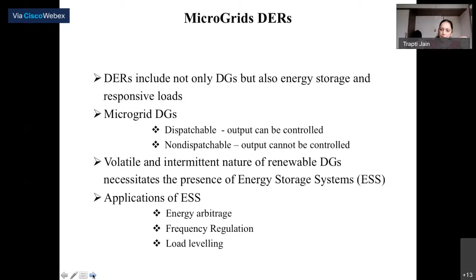We need to maintain the frequency. As shown in the first figure, 60 hertz is the frequency we want to maintain, and the allowable band is 59.95 to 60.05. Within this band, the frequency should be maintained. Initially, the frequency was within this band, so we were not using the ESS, and the stored energy was constant. But then the frequency starts increasing above 60.05. To maintain the frequency within the desired band, we can charge the energy storage system, and as soon as the frequency comes back within the desired band, we stop this charging.